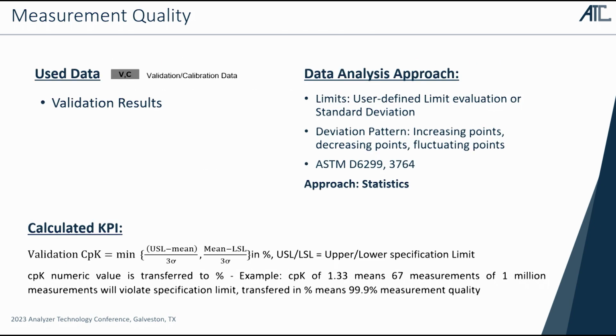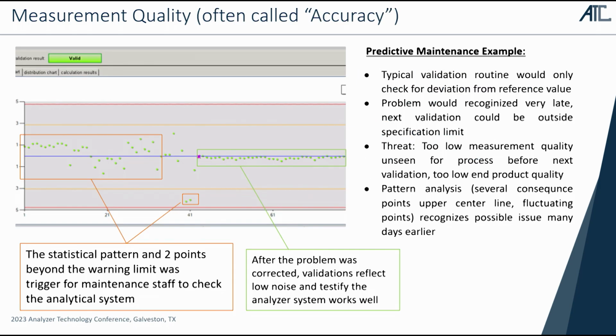Second topic, measurement quality, an often underestimated topic. What we see is how to use validation results. In the field, you do a validation, sometimes manually, sometimes automated, checking for deviation with a reference gas, for example. But in some cases, we also see a more enhanced approach. One of the topics is the classical deviation pattern. If you have some consecutive increasing points, some decreasing points over time, or some fluctuation, that already shows there's an issue. Using a standard, ASTM D6299 and D3764 are the standards to go to. We're using a purely statistical approach here to analyze this information. There were a lot of papers in the past ATCs about the importance of validation and how to evaluate it, so I didn't focus on that topic this time, but gave a short explanation of what we see.